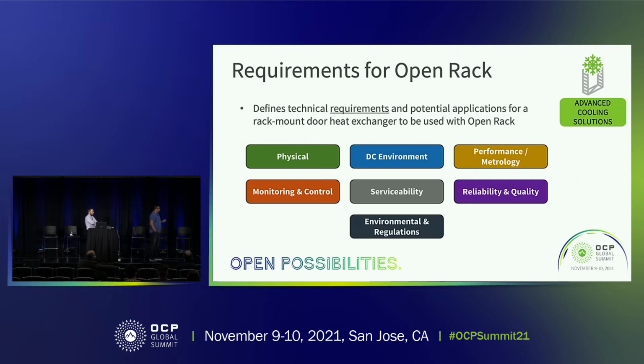How do you define performance and metrology? How do you determine the cooling capacity of a door heat exchanger? We have monitoring and control, in terms of defining the required and the recommended sensors, controls, and alarms. We have serviceability, which is very important. Obviously, a door heat exchanger is a massive assembly.